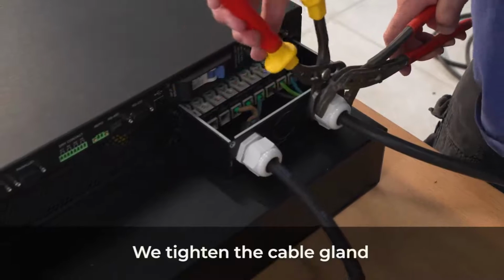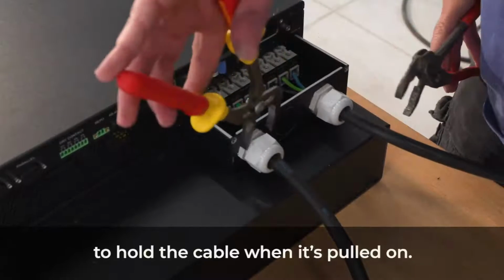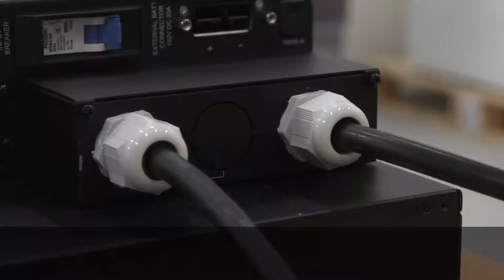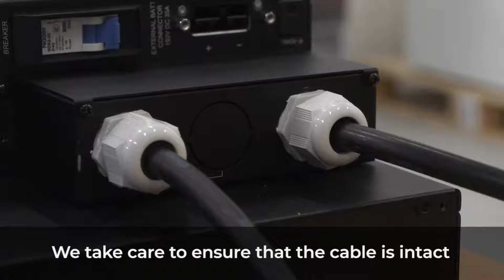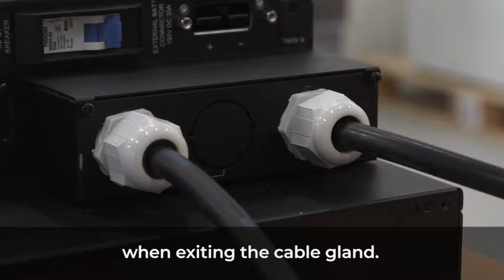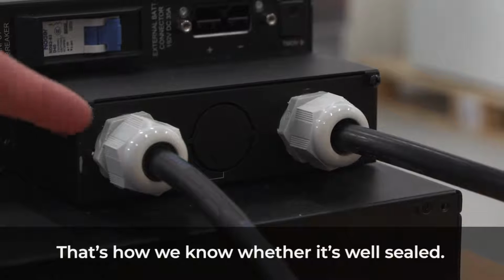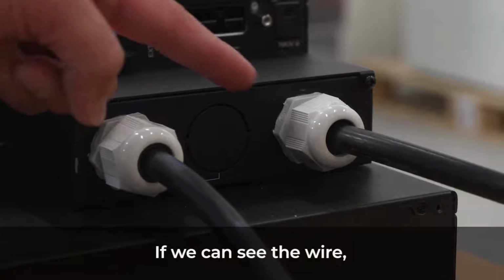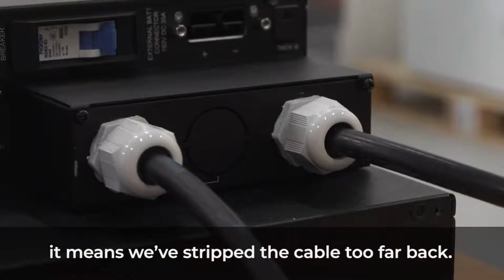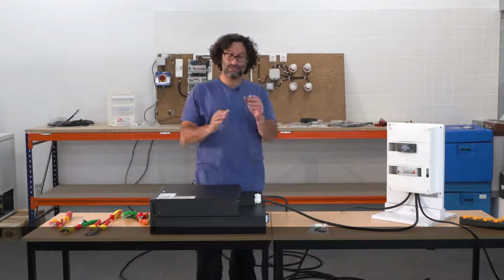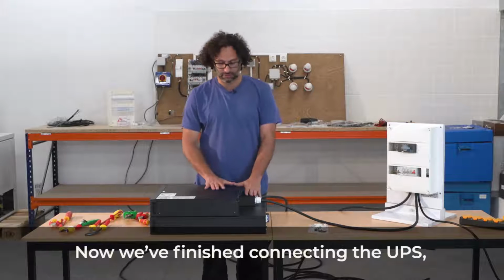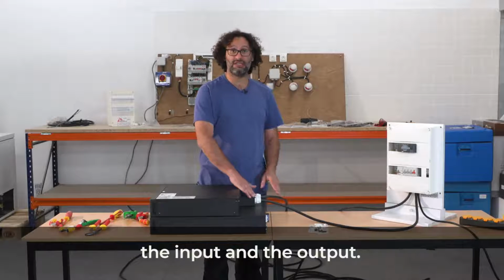We tighten the cable gland to hold the cable when it's pulled on. We take care to ensure that the cable is intact when exiting the cable gland. That's how we know whether it's well sealed. If we can see the wire, it means we've stripped the cable too far back. Now, we've finished connecting the UPS, the input and the output.